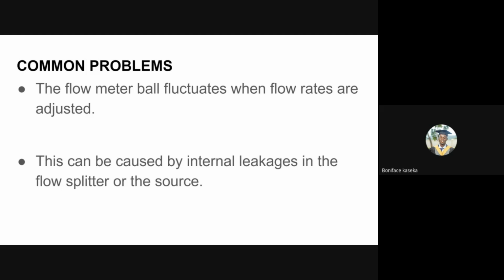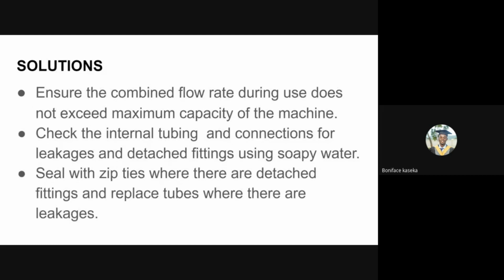There are several causes that can lead to such a problem, but the main one could be an internal leakage. It could be an internal leakage in the oxygen flow splitter or the tubing, or, if you're using an oxygen concentrator, a leakage inside the concentrator. Then its ability to deliver oxygen to the oxygen flow splitter will be compromised, and as such you cannot have a stable flow of oxygen into the oxygen flow splitter. So those are the possible causes. On the next slide, we're going to look at the possible solutions to that problem.